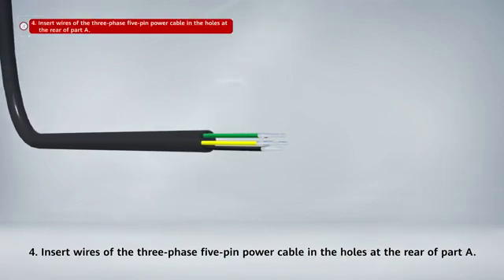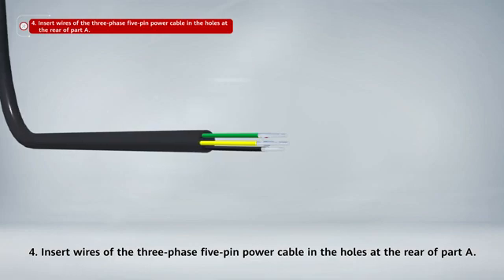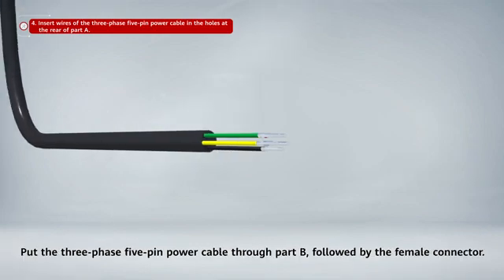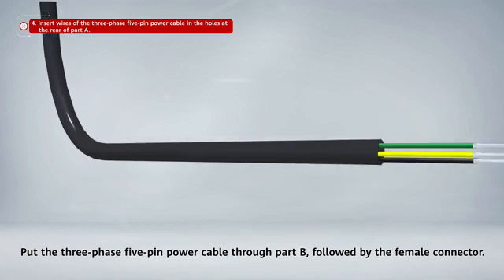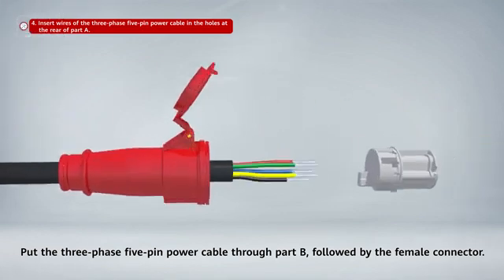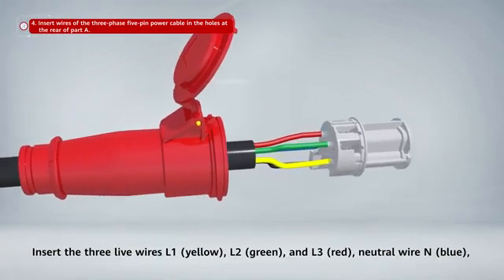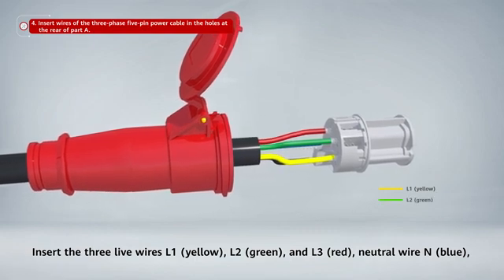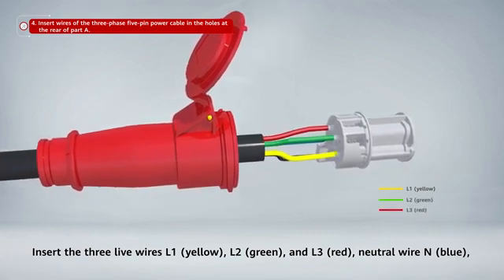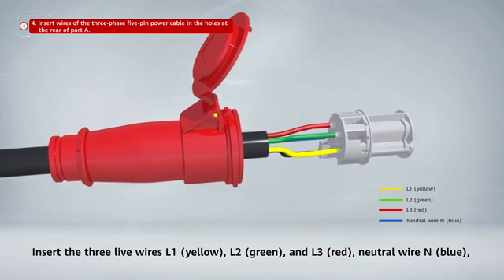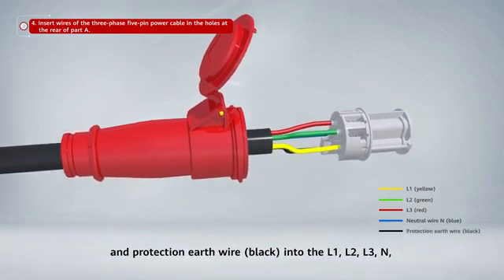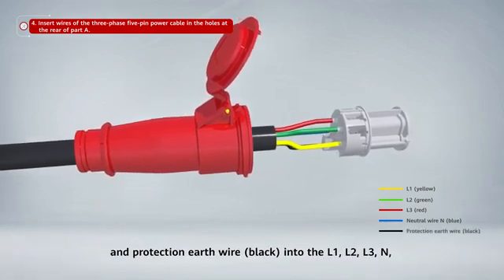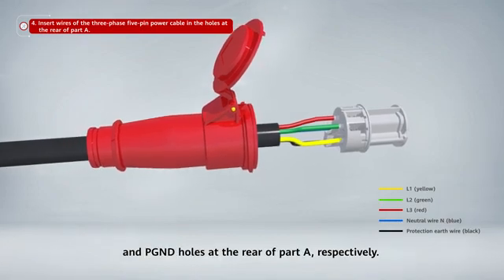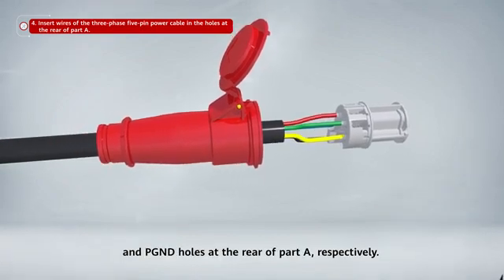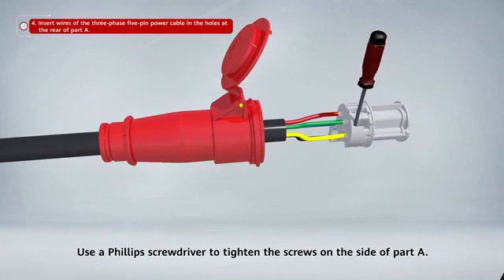4. Insert wires of the three-phase 5-pin power cable in the holes at the rear of Part A. Put the three-phase 5-pin power cable through Part B, followed by the female connector. Insert the 3 live wires L1 yellow, L2 green, and L3 red, neutral wire N blue, and protection earth wire black into the L1, L2, L3, N, and PE holes at the rear of Part A, respectively. Use a Phillips screwdriver to tighten the screws on the side of Part A.